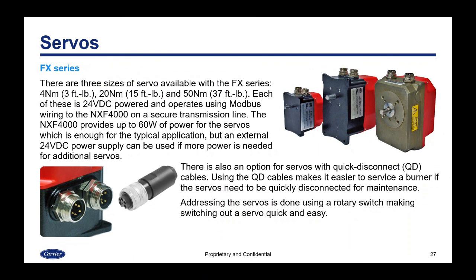The servos that we use with the NXF4000 are the FX series, and there's also a presentation on FX servos available on the YouTube channel. There are 3 sizes of servos available: a 4 Newton meter or 3 foot-pound, a 20 Newton meter or 15 foot-pound, and a 50 Newton meter or 37 foot-pound. Each of these is 24 volt DC powered and operates using Modbus wiring to the NXF4000 on a secure transmission line. The NXF4000 provides up to 60 watts of power for the servos, which is enough for the typical application, but if you need more power, an external 24 volt power supply can be used as well.